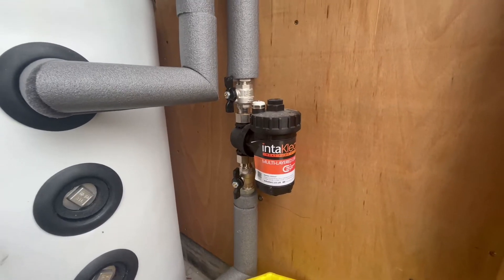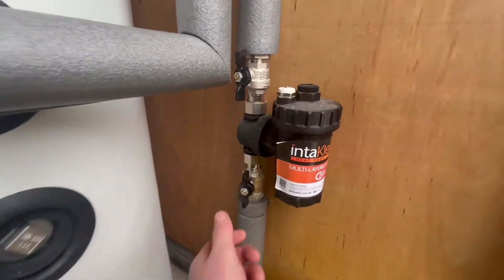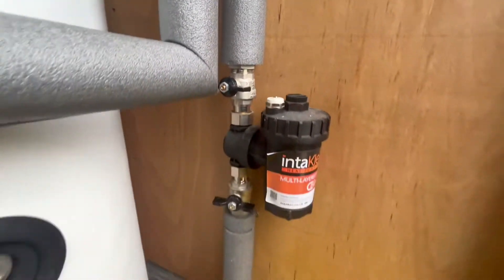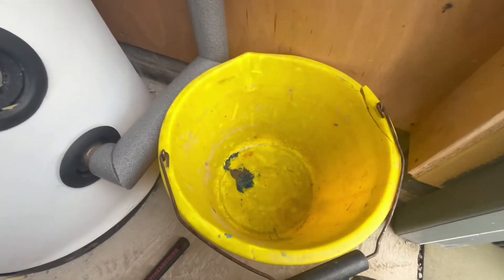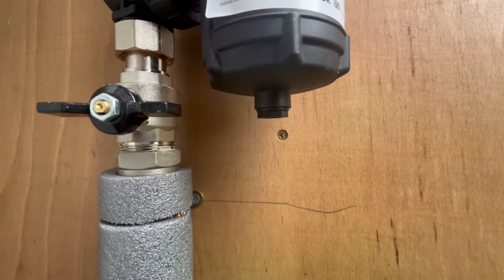To check your IntaKleen filter, you'll first need to switch off your heating system and give it a couple of minutes to cool down a bit. Then we need to isolate the valves. Then we need to get a tub or a bucket, place it underneath so we can drain off from the little vent below.